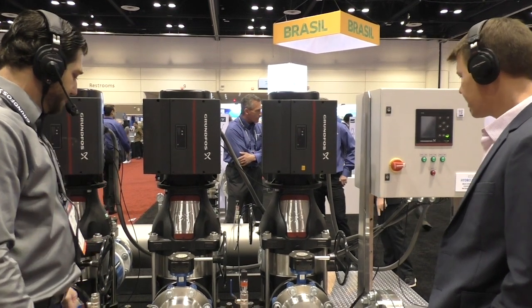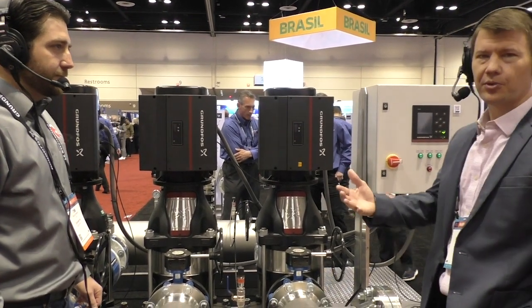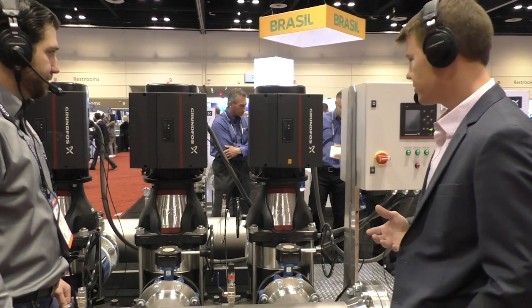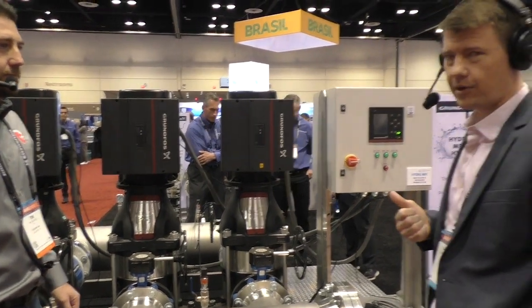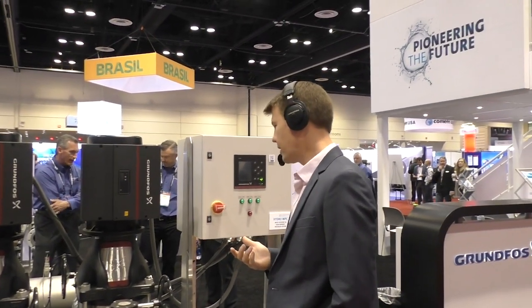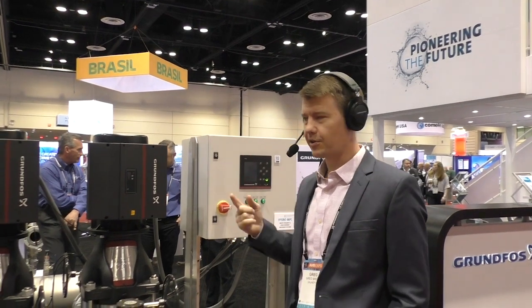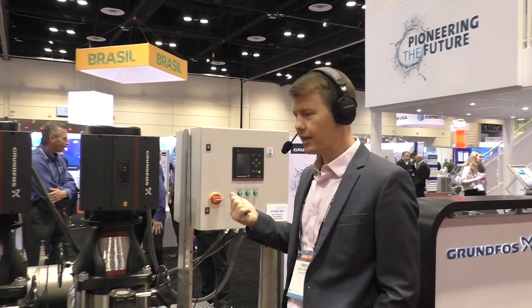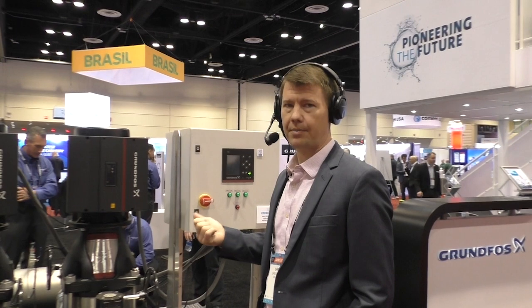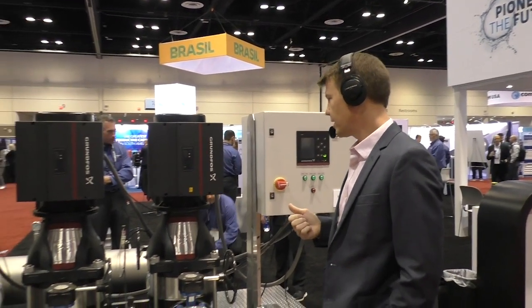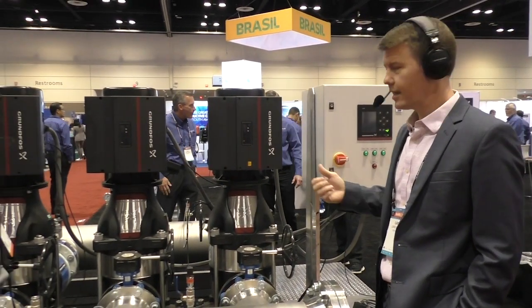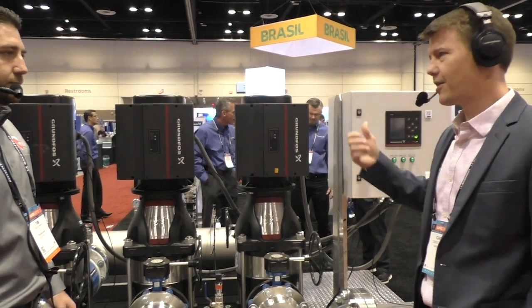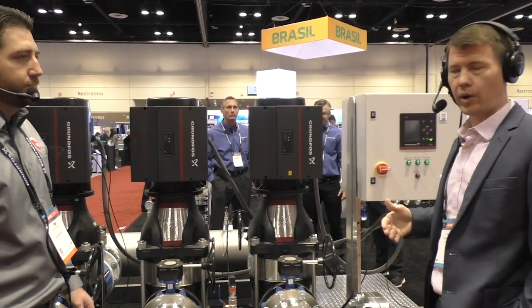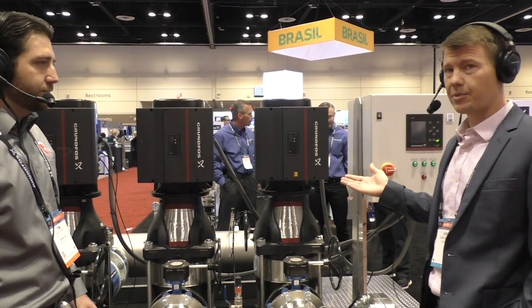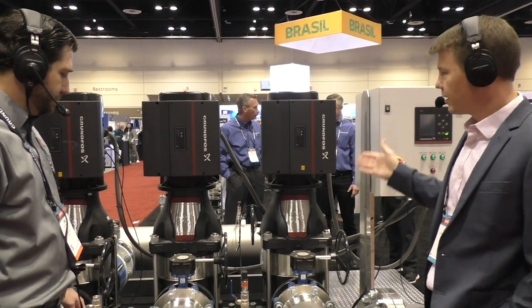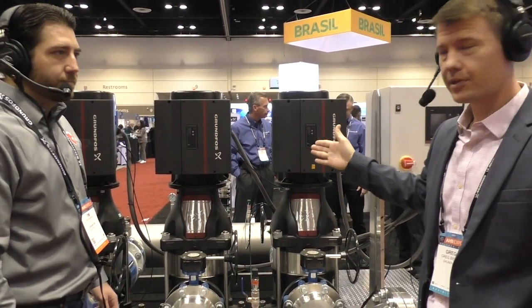Sure, yeah. This is the Hydro MPC, as you said. Most people know it for the domestic boosting application, but Grundfos is all about pioneering the future. You walk around the booths in this building, you're not going to see any pumping systems like this. This is a great product for the HVAC application, mainly because HVAC systems are designed around the high load point, and they don't typically run there. About 80% of the time they're running at part load. This system allows us to only run the pumps when they're needed.